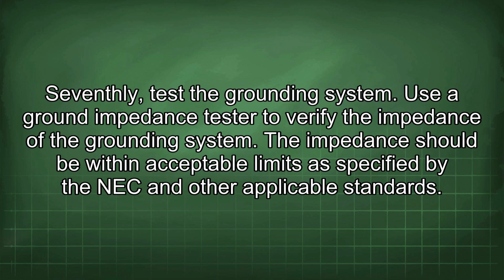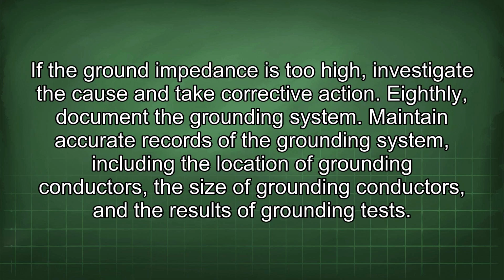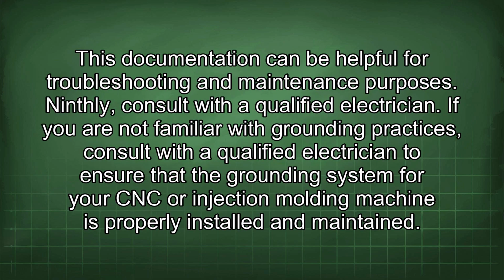Seventhly, test the grounding system. Use a ground impedance tester to verify the impedance of the grounding system. The impedance should be within acceptable limits as specified by the NEC and other applicable standards. If the ground impedance is too high, investigate the cause and take corrective action. Eighthly, document the grounding system. Maintain accurate records of the grounding system, including the location of grounding conductors, the size of grounding conductors, and the results of grounding tests. This documentation can be helpful for troubleshooting and maintenance purposes. Ninthly, consult with a qualified electrician. If you are not familiar with grounding practices, consult with a qualified electrician to ensure that the grounding system for your CNC or injection molding machine is properly installed and maintained.